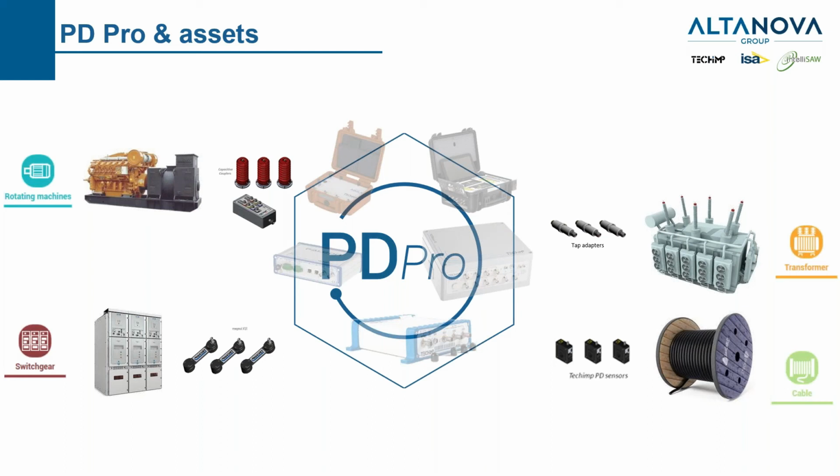Maybe we have a population of 15 transformers. They all have the same manufacturer, but we have seen that there is different data resulting from one manufacturer of bushing with respect to another, and this information can be stored and made more available on the DB.